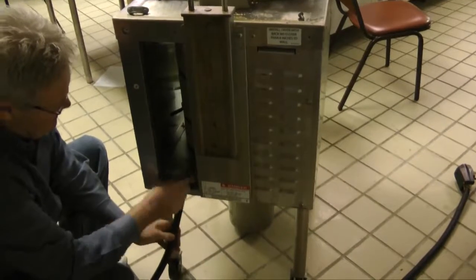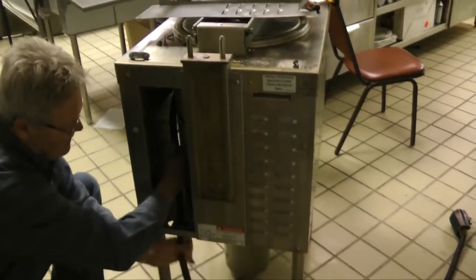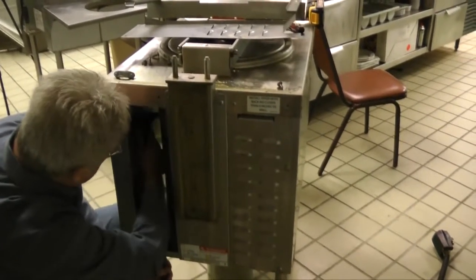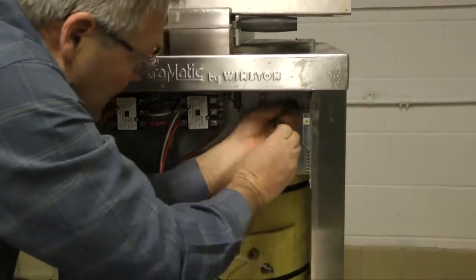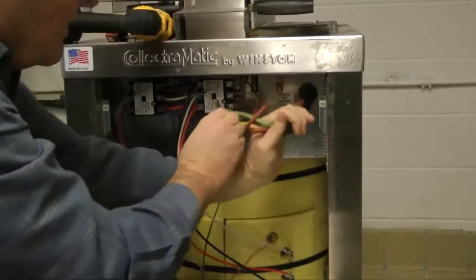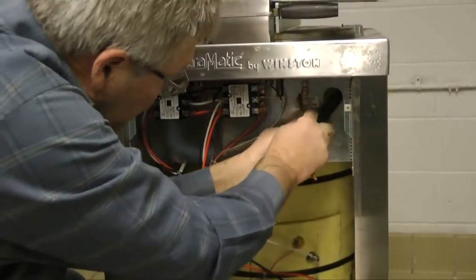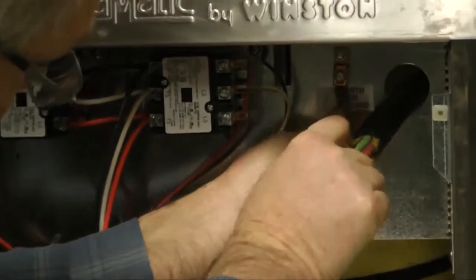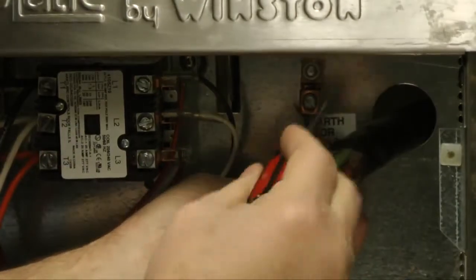Begin the installation of the new power cord by threading the wires through the access point in the back of the fryer. Ensure the power cord wires are completely pulled through the small hole in the front of the fryer. Install the green ground wire by inserting the wire into the compression screw assembly, labeled earth or ground, located to the left of the power cord access point on the front of the fryer.